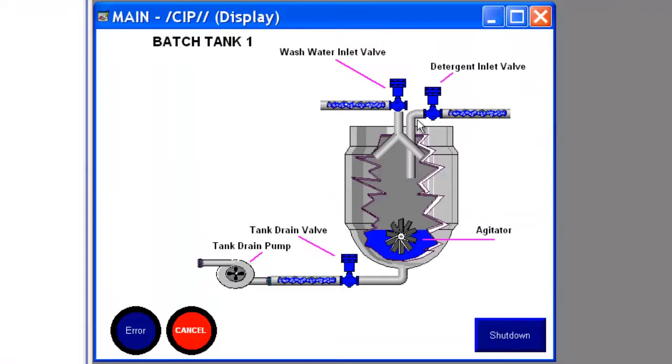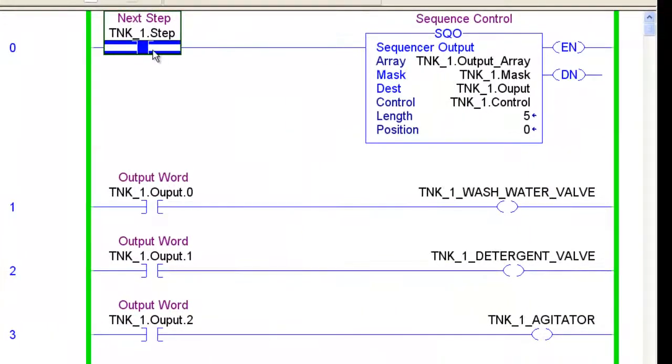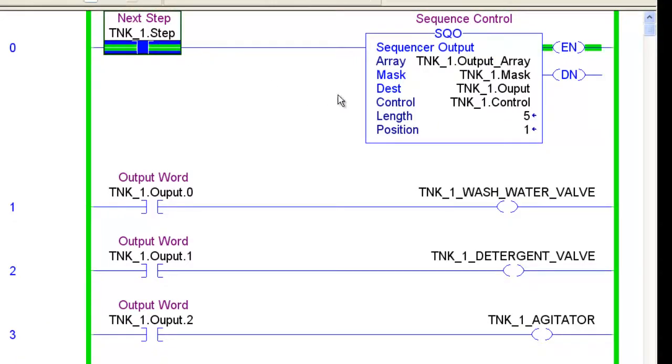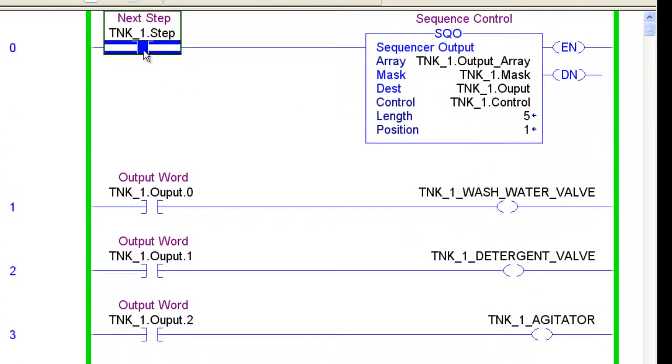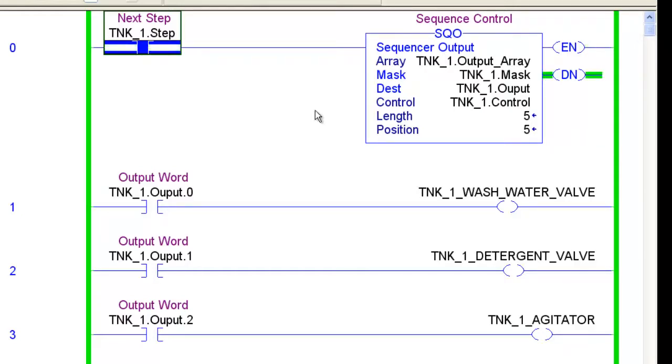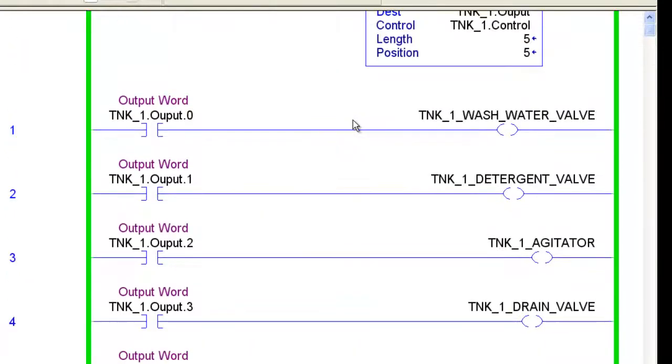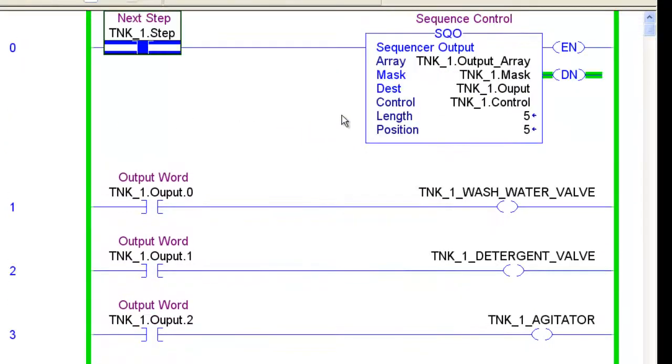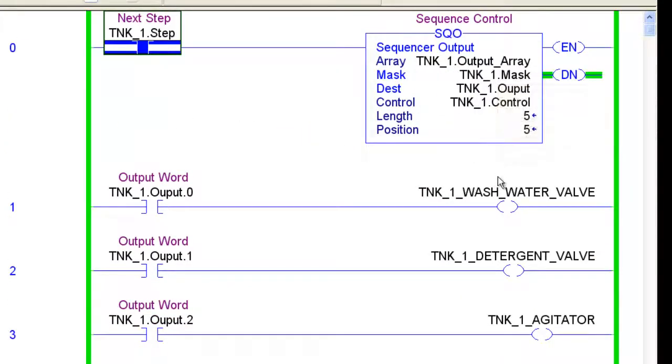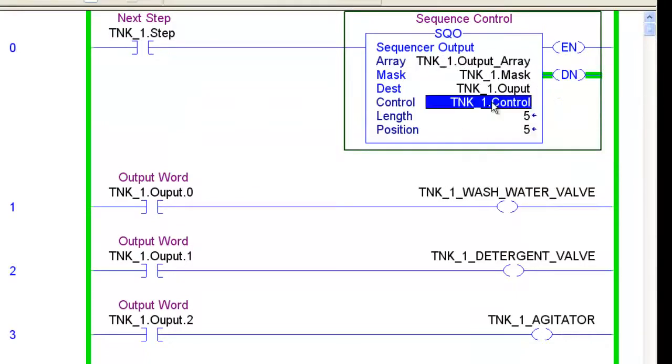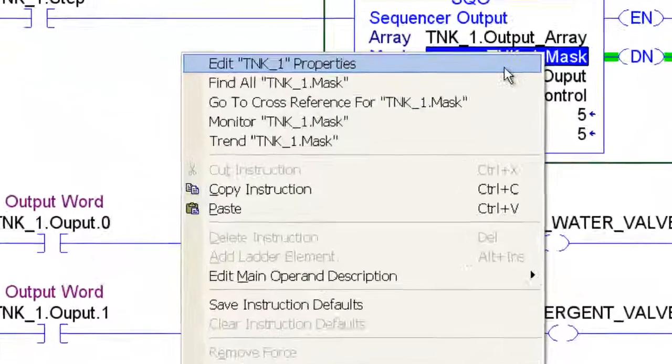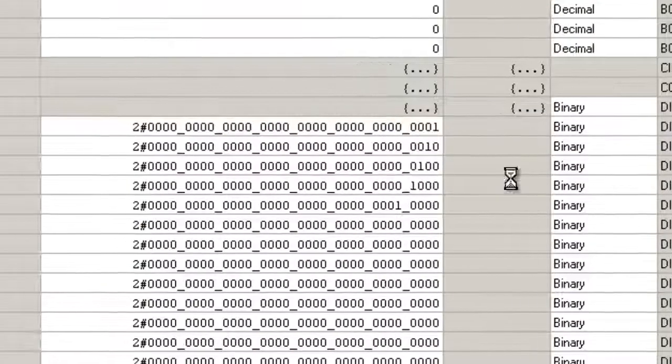Here's our batch tank. Once again, everything's off. So we're at position zero. If I go ahead and start stepping through this, that's a control T by the way, control toggle. You can notice we're at step one. Nothing's turned on. What we should have done is loaded data from our array into our output. As I step through here, something's obviously wrong. I believe it's the mask. What I failed to do was load any data in the mask, so it filtered everything from my array. It's no problem.